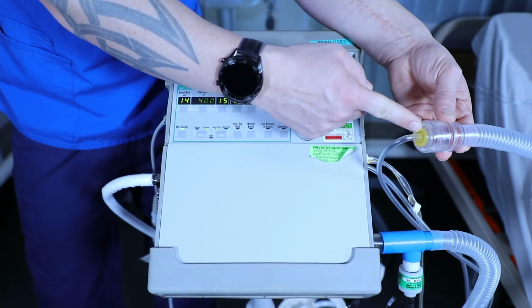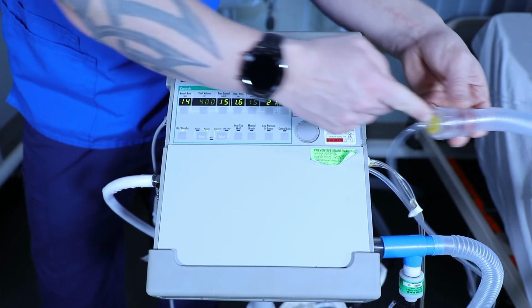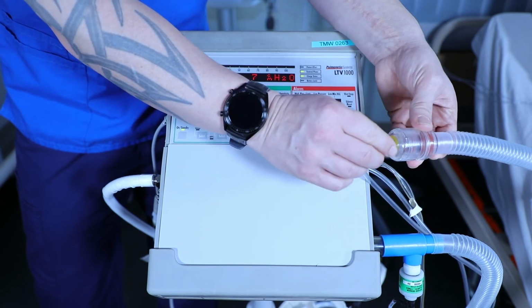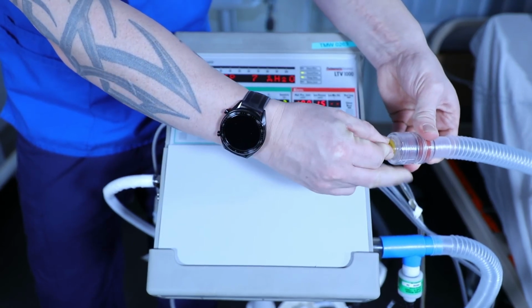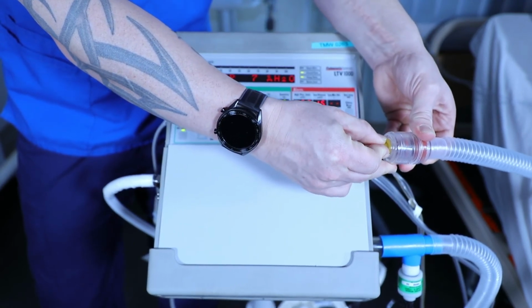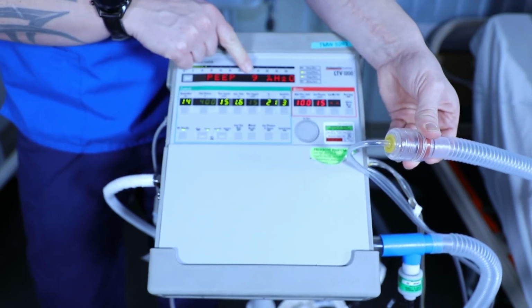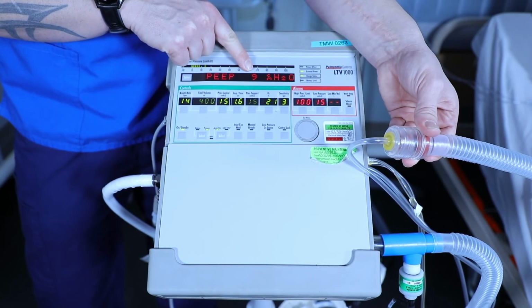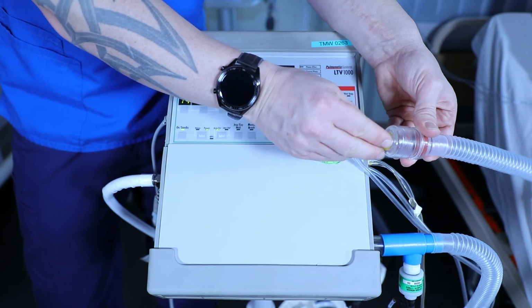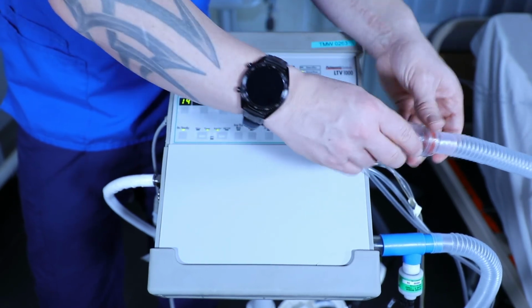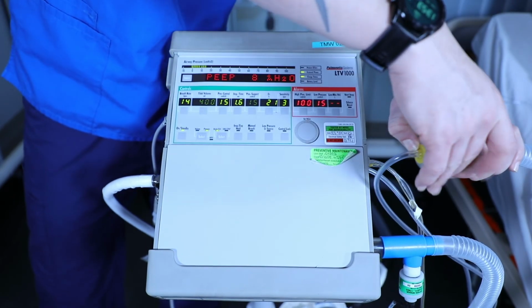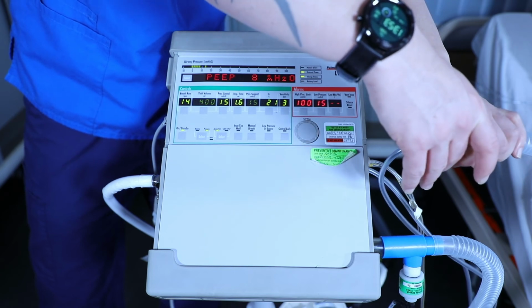To change the PEEP valve, we want to press the yellow button in, and we turn the dial simultaneously, and we can see that we've now gone up to 9 centimeters of water of PEEP. So if we try and put this down to 5, we press the yellow button and we turn it slowly.